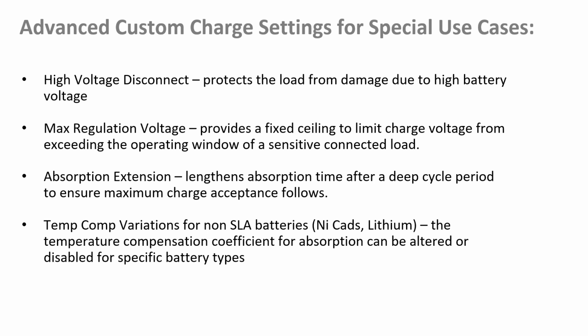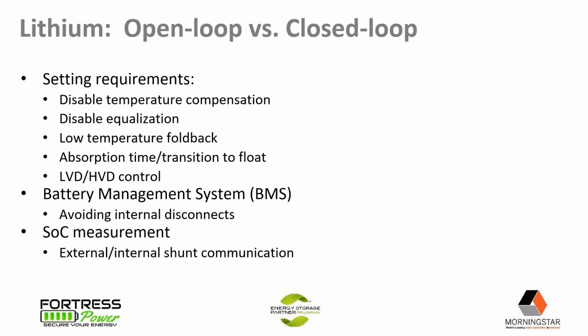Lastly, we have the ability to provide temperature compensation changes. In the case of lithium, temperature compensation is actually disabled because they want a consistent voltage applied across the terminals. But in a lot of other chemistries, for instance nickel cadmium, there's a completely different charge profile and temperature compensation than lead acid, and of course than lithium. So we allow all of that to be programmed.